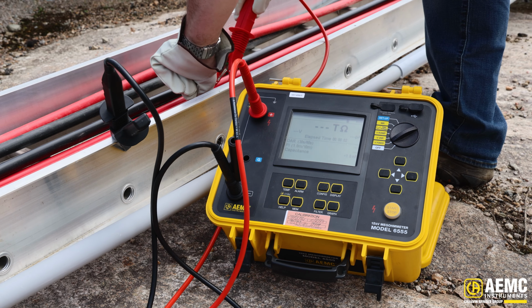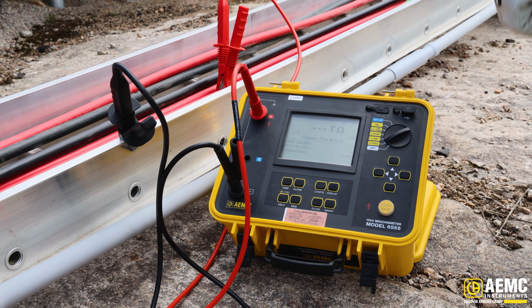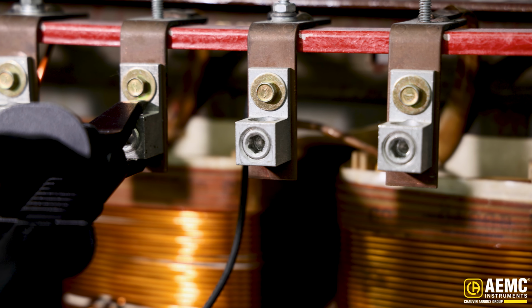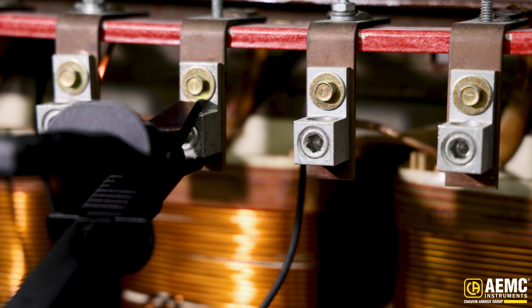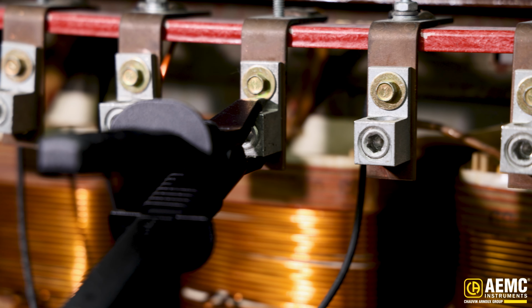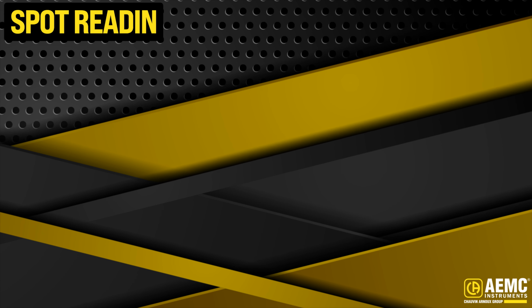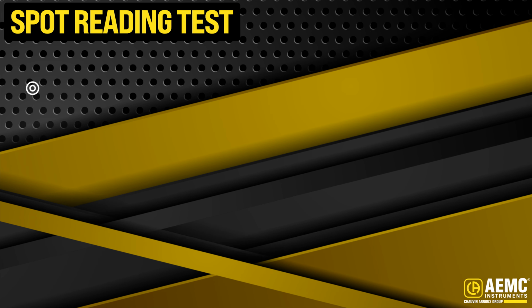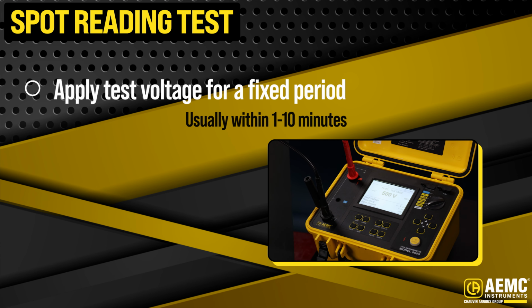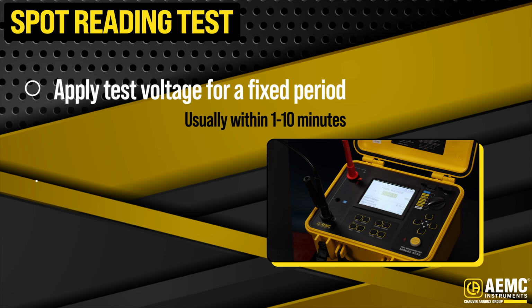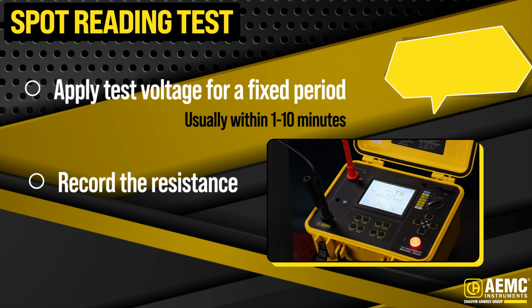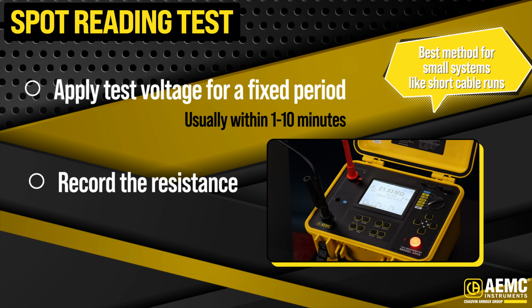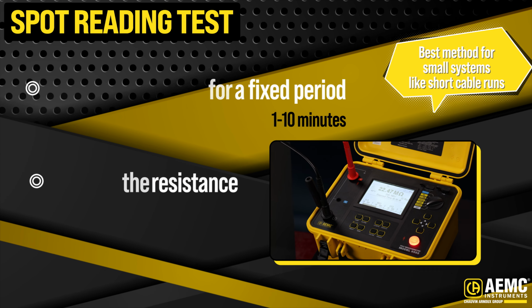There are 3 common ways to measure insulation resistance. Each offers different insights depending on the equipment and environment. Let's break them down. The spot reading test is the simplest method. Apply test voltage for a fixed period, usually within 1 to 10 minutes, then record the resistance. It's best for small systems with little capacitance, like short cable runs.